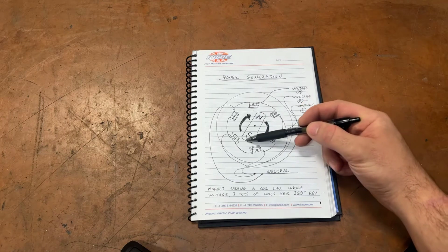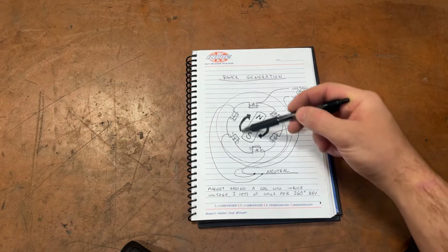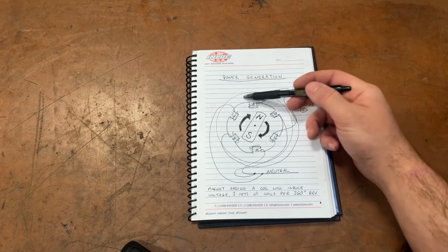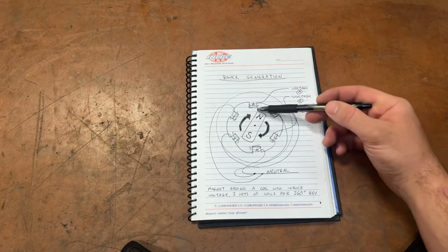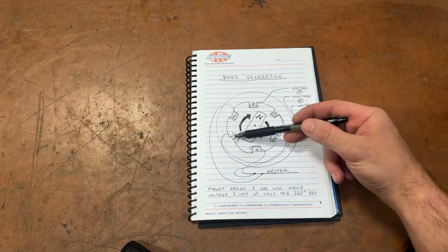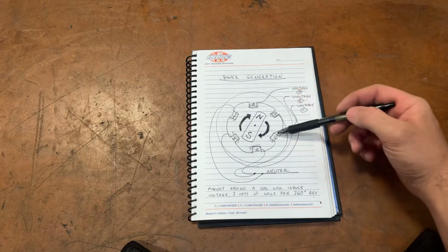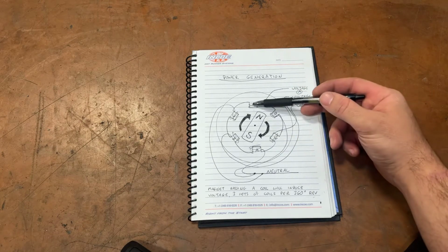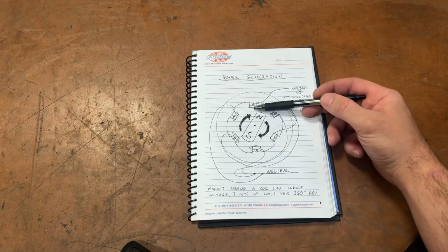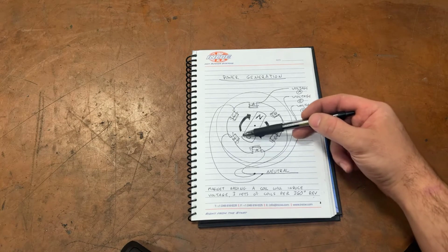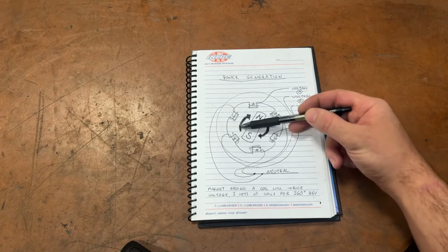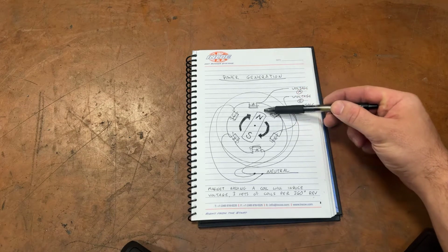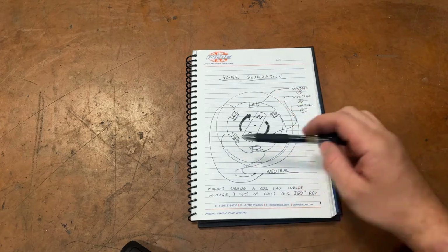This is a big, giant, permanent magnet, okay? We call this a rotor inside of a motor. The outside part is called a field frame. You'll see these 3 sets of coils here. So there's 6 coils in here. All right, but there's sets, one on the north pole, one on the south pole. As this guy is spinning, this magnet spins past the presence of a coil and induces a voltage into it.